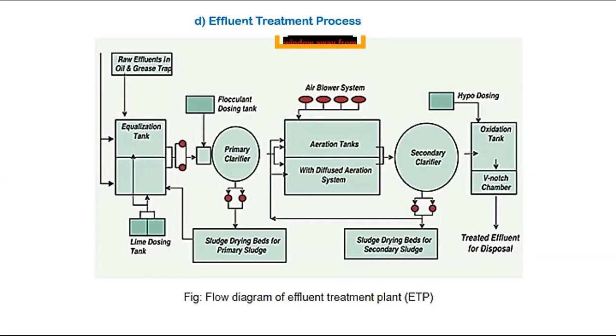After that, treating in the STP, if you are feeding 100 KLD into the STP, there are a lot of losses happening due to the process. If you are going to remove the sludge and you are adding water, chemicals and everything, there is a lot of evaporation also. After the losses, you will get only 80% from the input water. So that's why loss is there every time.